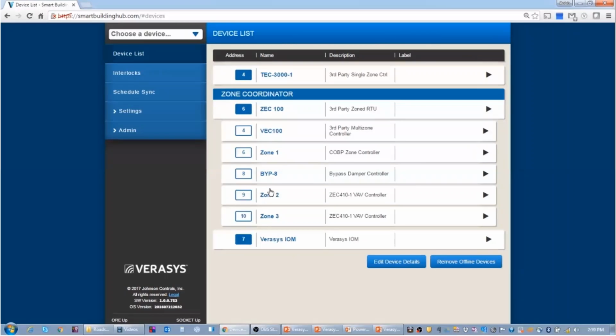As I said before, in a Niagara environment, the supervisor controller keeps track of all the data on the bus and organizes it. In the supervisor, you must map each point from the field controller to a particular address before you can do anything with it. After it's mapped, then you can create alarms, add trends or schedules. It's a lot of work to organize all this data using a supervisory controller.